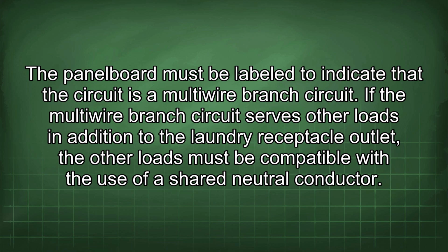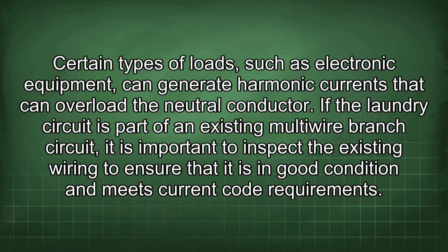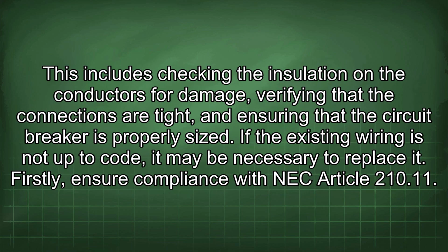If the multiwire branch circuit serves other loads in addition to the laundry receptacle outlet, the other loads must be compatible with the use of a shared neutral conductor. Certain types of loads, such as electronic equipment, can generate harmonic currents that can overload the neutral conductor. If the laundry circuit is part of an existing multiwire branch circuit, it is important to inspect the existing wiring to ensure that it is in good condition and meets current code requirements. This includes checking the insulation on the conductors for damage, verifying that the connections are tight, and ensuring that the circuit breaker is properly sized. If the existing wiring is not up to code, it may be necessary to replace it.